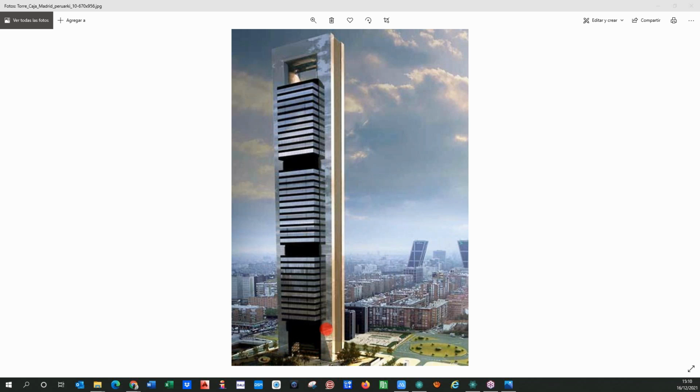These are the words from the owner of the building, the previous owner, and the maintenance responsible. It was not working because the problem is that there are 34 floors in this building, and there are two different faces. This is the north face and the south face is identical. So there are 68 semi-floors, we can say, in this building, and in every single semi-floor we have 34 shutters.